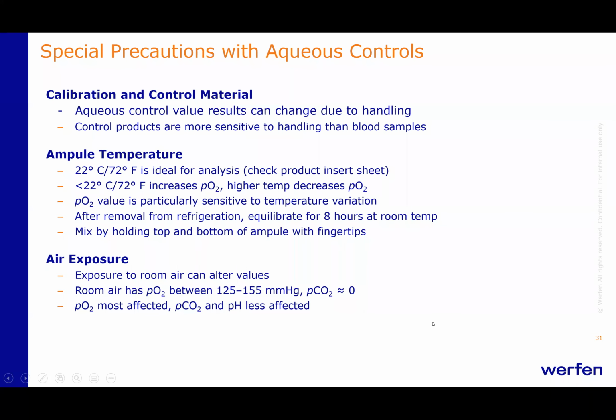And finally, special precautions with aqueous controls. Most blood gas controls are aqueous. Aqueous control values can change due to handling. Control products are much more sensitive to handling than blood samples. So there are temperature issues as well as air exposure issues. So both should be controlled: ampule temperature should be very close to what the manufacturer recommends, and minimum time should pass from opening the ampule to analysis.